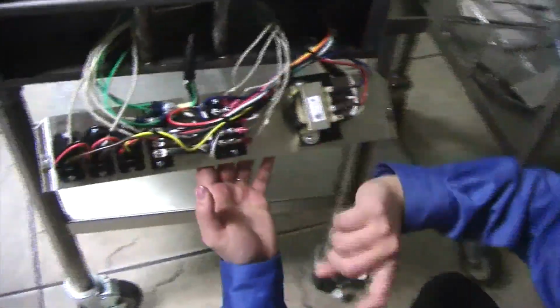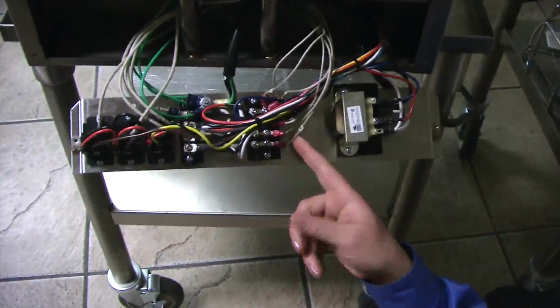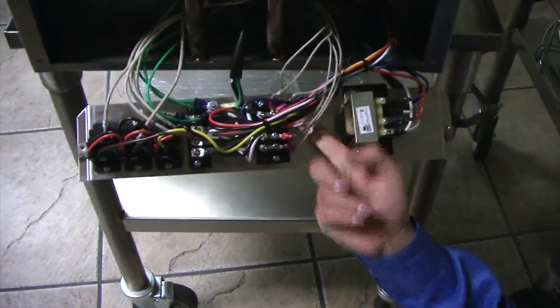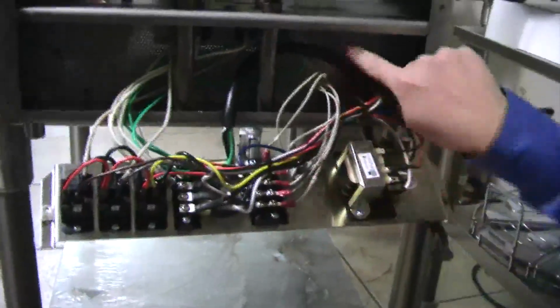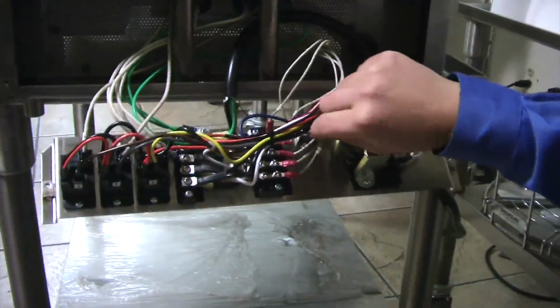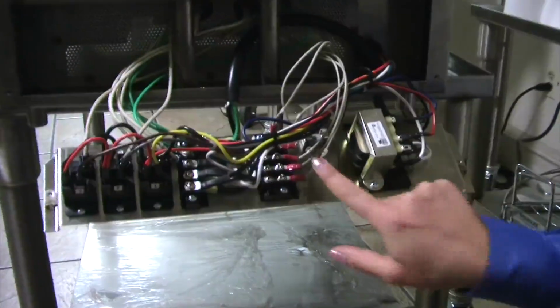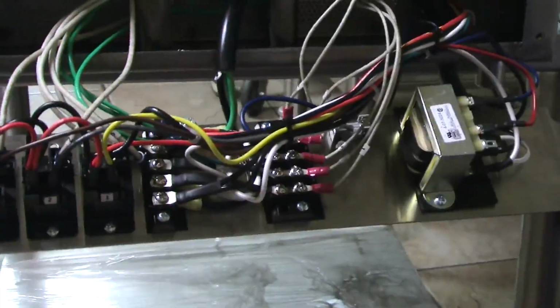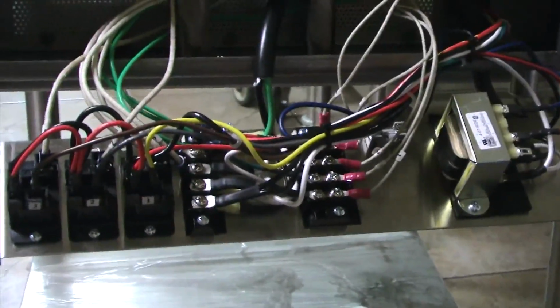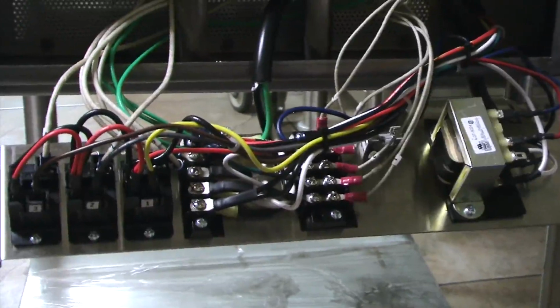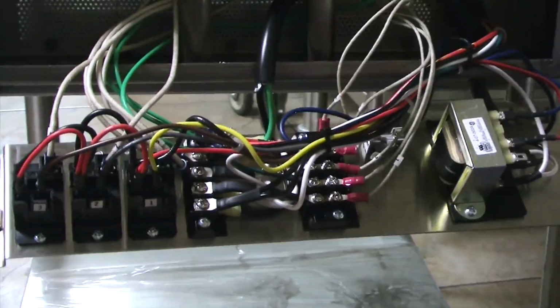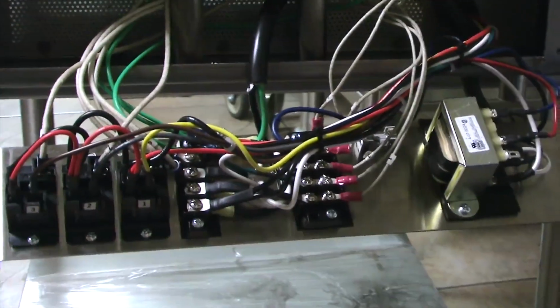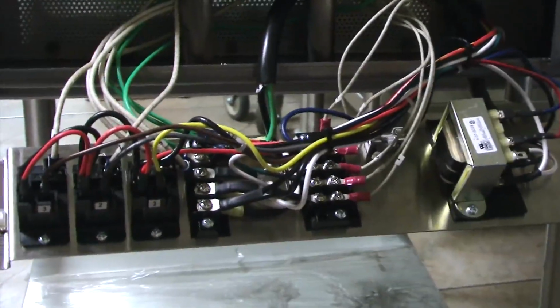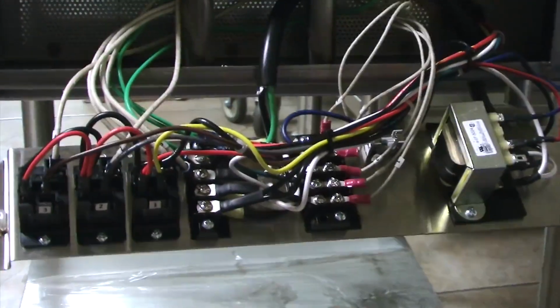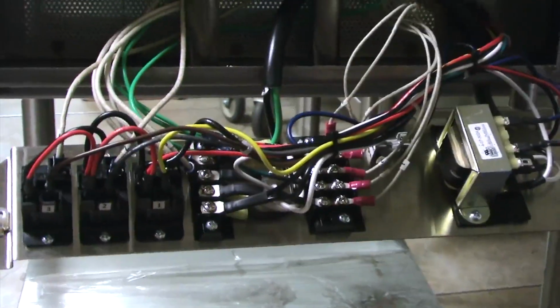Checking your sensors. Your sensors from the control board come here to the terminal block. They're numbered for you, 1, 2, 3, and then your 4. So obviously, zone 1 would be the bottom, zone 2 would be the upper left, and zone 3 will be your upper right. You want to check your sensors at room temp. I would say around 70 degrees, you might get around 2,000 ohms. If it's under 2,000 ohms, that's a good indication that your sensor's not working. If it goes higher, to 3,000, 4,000, that's because your machine is hot, and it's obviously going to read a lot higher.